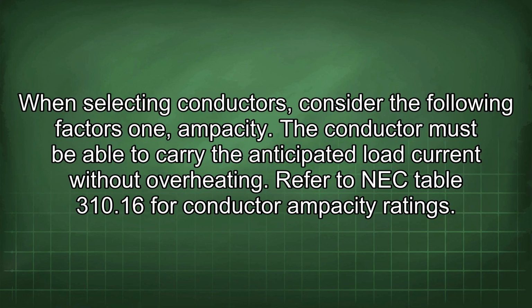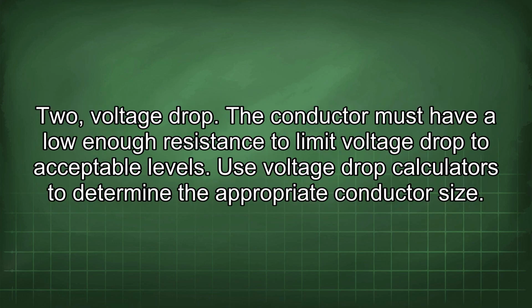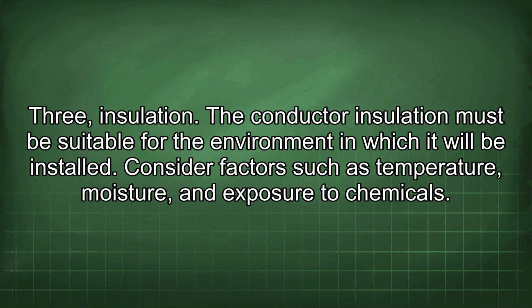When selecting conductors, consider the following factors. 1. Ampacity. The conductor must be able to carry the anticipated load current without overheating. Refer to NEC Table 310.16 for conductor ampacity ratings. 2. Voltage drop. The conductor must have a low enough resistance to limit voltage drop to acceptable levels. Use voltage drop calculators to determine the appropriate conductor size. 3. Insulation. The conductor insulation must be suitable for the environment in which it will be installed. Consider factors such as temperature, moisture, and exposure to chemicals.